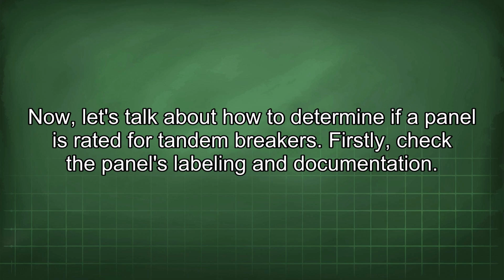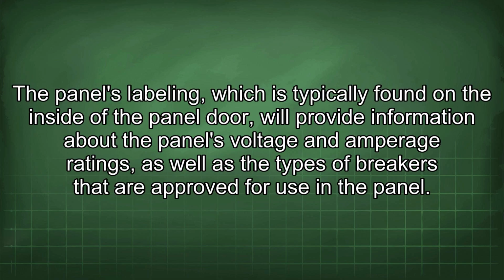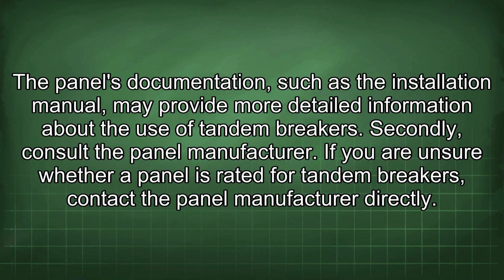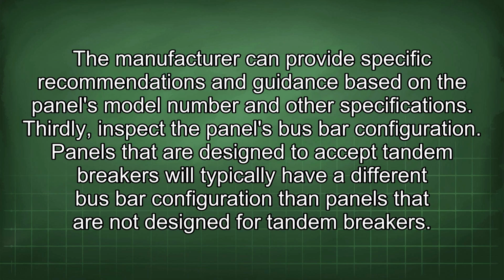Firstly, check the panel's labeling and documentation. The panel's labeling, which is typically found on the inside of the panel door, will provide information about the panel's voltage and amperage ratings, as well as the types of breakers that are approved for use in the panel. The panel's documentation, such as the installation manual, may provide more detailed information about the use of tandem breakers. Secondly, consult the panel manufacturer. If you are unsure whether a panel is rated for tandem breakers, contact the panel manufacturer directly. The manufacturer can provide specific recommendations and guidance based on the panel's model number and other specifications.